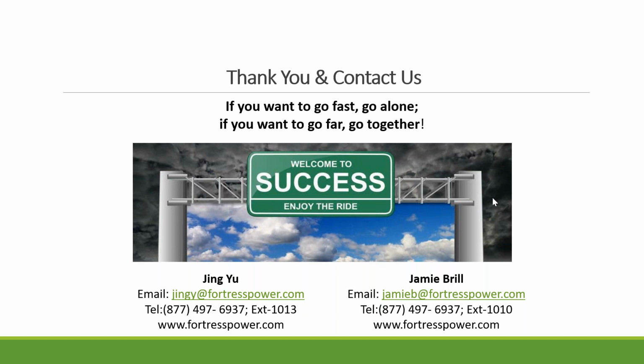This is an inverter software application, especially for time of use. Most inverters let you set up a time window to shave the demand charge. If you want to do peak load shaving, or demand curtailment, some inverters can do it and some cannot, then you need a third party unit. We actually do work with a third party company that has a control unit to help curtail demand charge, especially for commercial buildings.